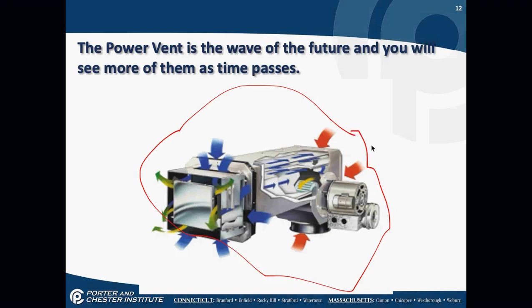Okay, the oil exhaust is very acidic. Okay, it contains a lot of acid, especially if it gets damp. It's very acidic. So the problem that occurs in a power venter is that little blower wheel that I've just circled. There's a little squirrel cage in here. This will start breaking down. It will start rusting and corroding. Okay, as that breaks down, there's a lot less suction that happens here.